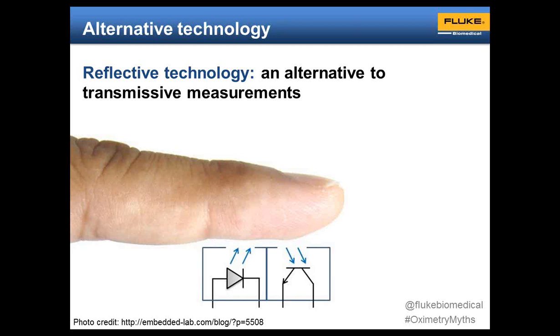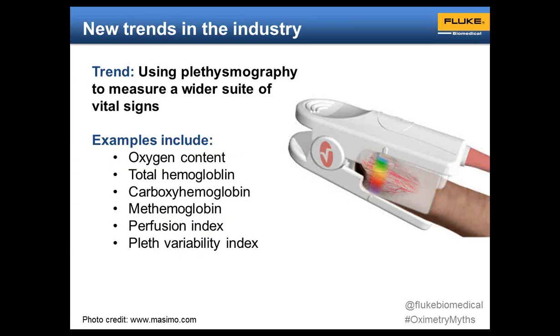There are other types of technology in this space, specifically the Masimo Rainbow set. It actually takes more than SpO2. There's a number of factors and measurements that it takes and displays, and therefore you need a slightly different tester to be able to test this. Masimo, along with others, are creating new ways to use plethysmography to measure a wider range of vital signs. There's some listed here, but there's also looking at glucose as well. So when you're looking at one of these sensors, you have to make sure that your tester is capable of testing all of the different parameters that are presented from the sensor, not just SpO2.